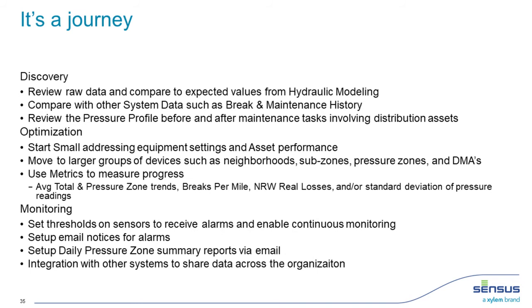The greatest benefit for me is probably making sure my PRVs are doing what they're supposed to be doing, that they're not broken, not out of adjustment. In the past you're always rolling a truck. A lot of utilities go out quarterly per year to look at their PRVs, kind of look at them and say 'I hope it's working,' and move on. So knowing every single morning that my pressure management is doing what it's supposed to be doing is key.